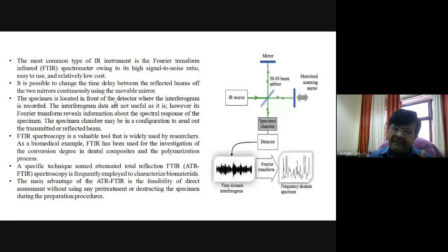The interferogram data are not useful as they are. However, its Fourier transform reveals the information about the spectral response of the specimen. Okay, the specimen chamber may be in a configuration to send out the transmitted or reflected beam here. And next, FTIR is a valuable tool that is widely used by researchers, for example in biomedicine. FTIR has been used for the investigation of the conversion degree in dental composites and the polymerization process.